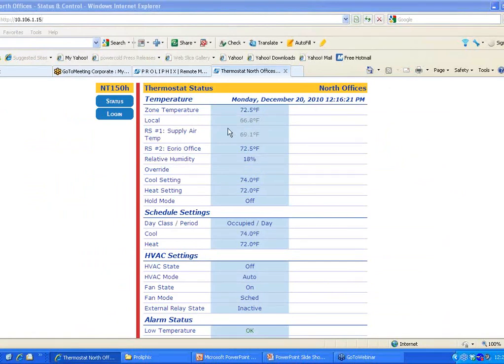This right here is a thermostat in one of our buildings, located in an office. You'll notice that I can see a lot of data, but I can't change anything right now, so it just tells me what's going on. The thermostat is controlling to a temperature of 72 degrees. The thermostat itself is in a space, I believe a closet, where it's 67 degrees. There's a remote sensor in the office reading 72, and that's the one we're controlling to.